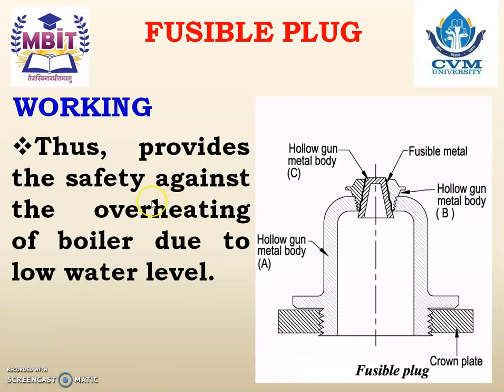This provides safety against overheating of the boiler due to low water level. If the water level indicator is watched properly and water is filled in time, the fusible plug will not activate. But if the water level continuously reduces — due to power failure or pump failure — it can overheat and ultimately blast the boiler. The fusible plug located below the minimum water level limit melts when exposed to steam and provides this safety.